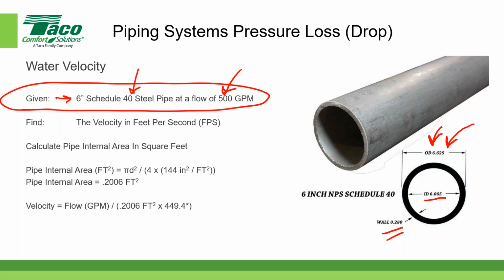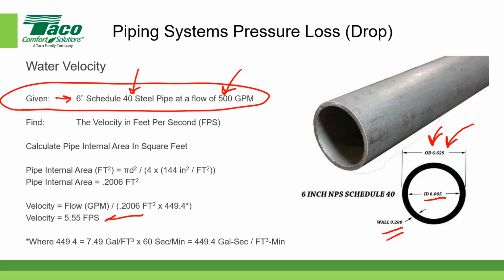And we know that the velocity is equal to the flow in gallons per minute divided by the cross-sectional area. And then we have that constant in there. I'll define that in a minute. And so our velocity comes out to 5.55 feet per second. And that little asterisk is the calculation that we use for making the conversion so that we wind up with feet per second. And so generally speaking, when we talk about hydronic systems, we always talk about the velocity in feet per second. So in our case here, it's 5.55 feet per second.